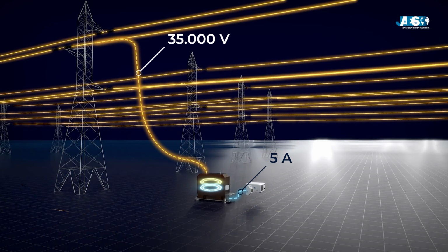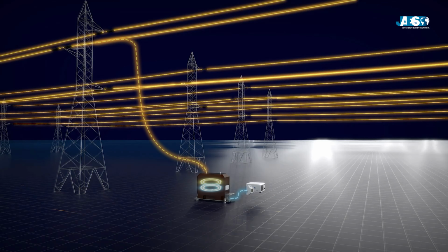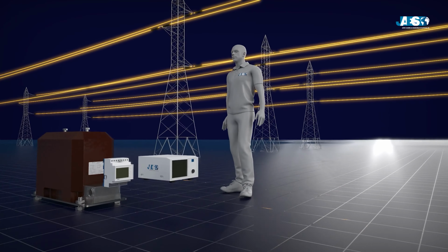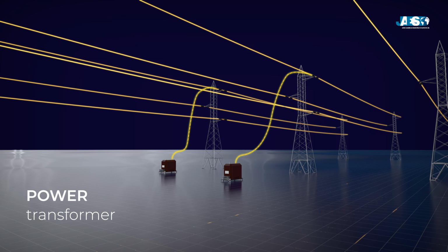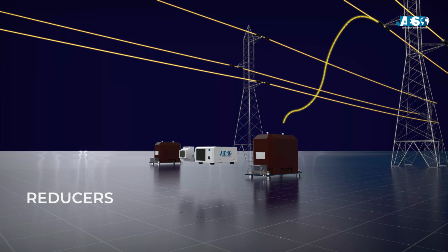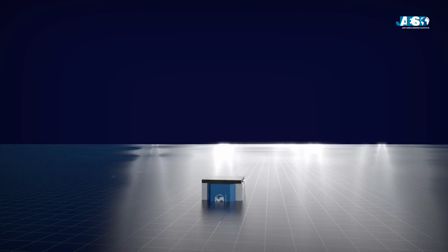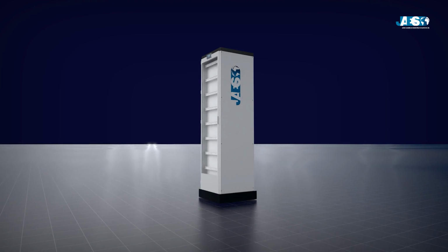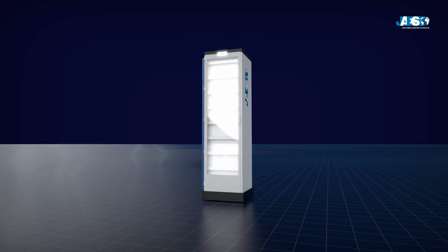Transformers electromagnetically reproduce an alternating current or voltage, which helps reduce heat dissipation problems and strong magnetic fields that can disturb measuring instruments, as well as isolating the operator from the rest of the system for safety. They are also called protection transformers when they help to manage the power and current flow on a network. Alternatively, when they have to carry measurement signals to instruments such as ammeters and voltmeters, they can be called reducers, precisely because they reduce the signal strength to facilitate reading. These devices are installed in switchboards of industrial plants where continuous monitoring of the energy flow is required, allowing the optimal operation of the entire plant.